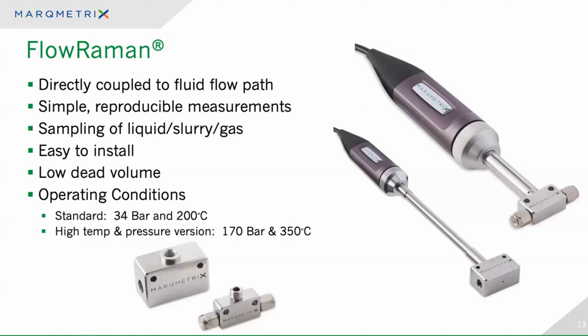One of our newest products is our Flow Raman. We got a patent for this earlier this year. It allows us to directly connect to any flowing system, whether that be liquid, slurry, or even flowing powders. We've done a lot of flowing powder work recently. We can directly couple that to our fluid flow path. It's simple, it's reproducible. It also takes advantage of our ball probe interface. We can sample, as I mentioned, liquids, slurries, or gases. It's easy to install. You can see in this one on the far right, it's simply 1/8 inch compression fittings. On the other, it's our higher pressure version. We sell the high pressure connecting nuts.